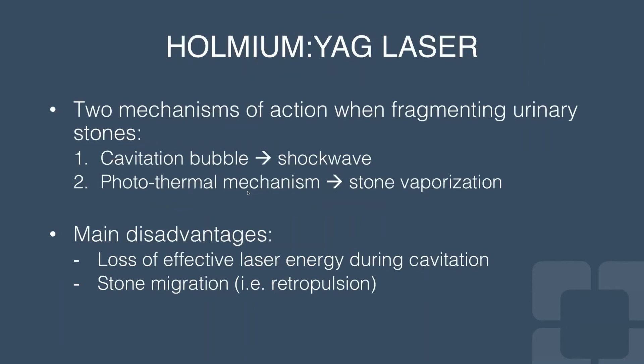How does the holmium YAG laser work? There are two different mechanisms of action when fragmenting urinary stones. The first is by way of a cavitation bubble, causing a shockwave — similar to our shockwave lithotripsy comminution mechanism. The second is a photothermal mechanism where the stone is vaporized. One main disadvantage is the loss of effective laser energy during the cavitation process, and stone migration or retropulsion is a well-known problem that minimizes the effectiveness of stone fragmentation.